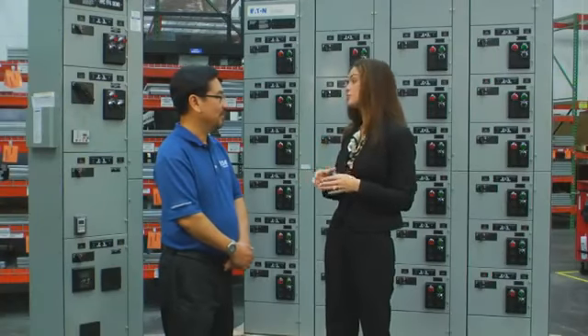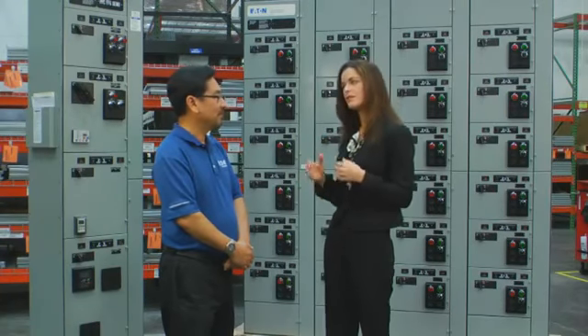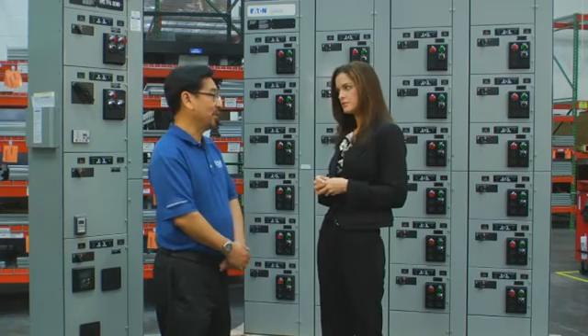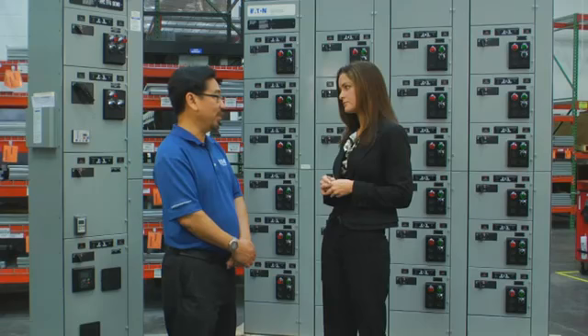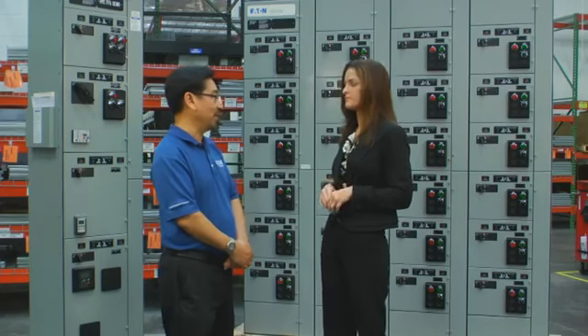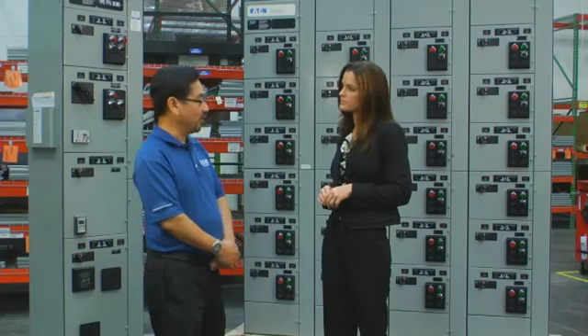Now, these are features intended to reduce the potential for an arc flash event, but we're not assuming that an arc could never happen. Absolutely not, because that's the kind of assumption that you just can't afford to make when dealing with the lives and safety of plant personnel. And that's why we've designed the FlashGard enclosure the way we have. For the safety of operational and maintenance personnel, we have designed the cabinet to be the main defense against the harmful effects of an arc flash event. We have very substantial steel panels and doors that, when securely latched, can suppress and contain the energy of an arc flash explosion. In essence, they form a barrier of protection between you and the potential danger that can be generated by an arc flash event.